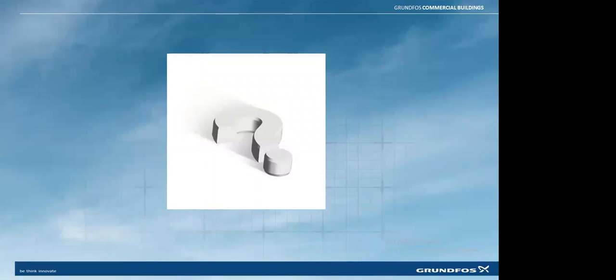So in case of any failure, both sensors still give a signal to our controller. If any one sensor fails, you will still continue to get a signal from the other sensor, with the warning. So this redundant primary sensor arrangement is available, sir. There is one more concept, having a primary sensor at the farthest point. There will be one sensor near the system itself, on the discharge header itself.